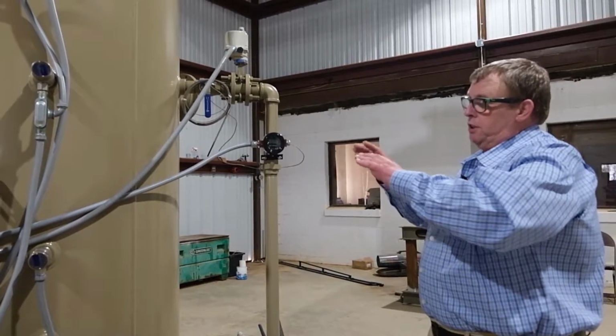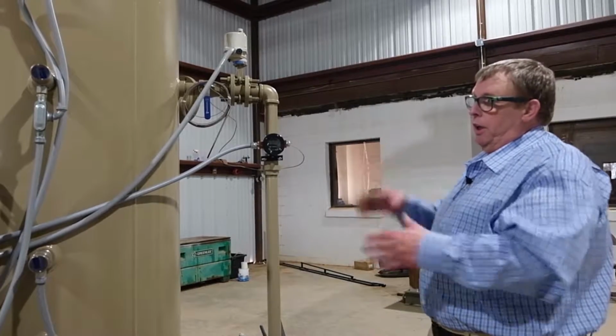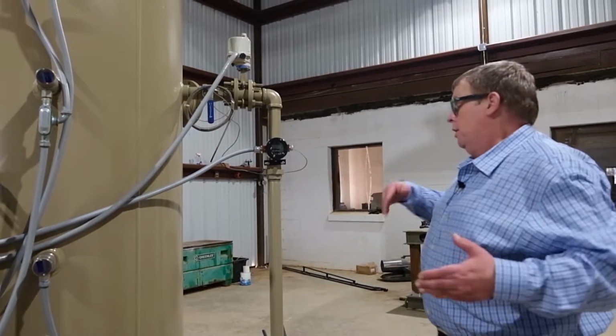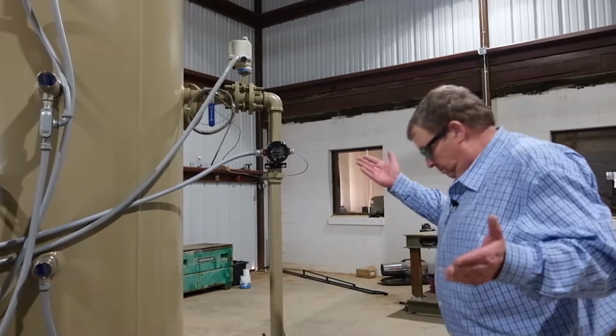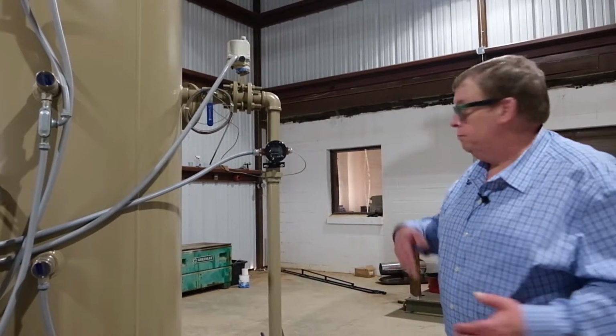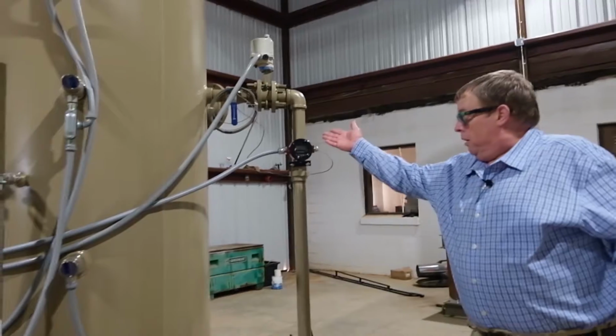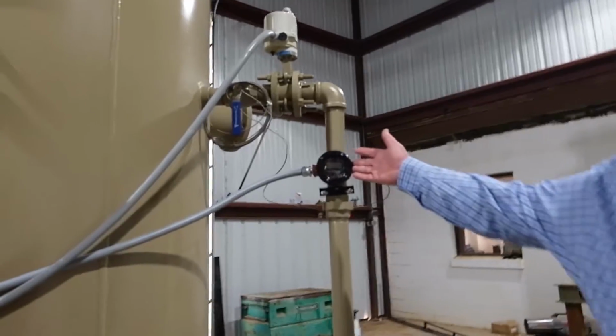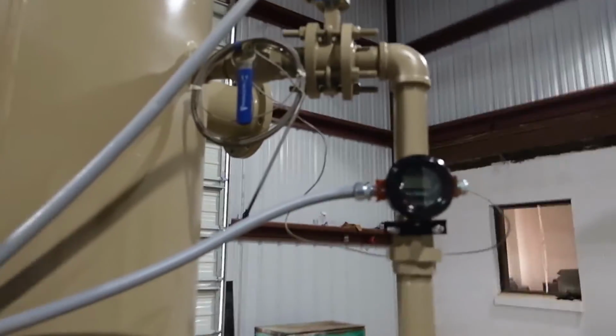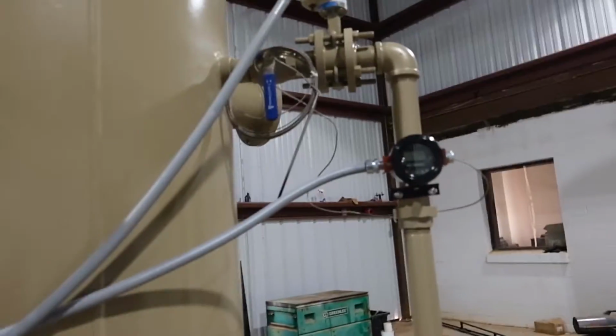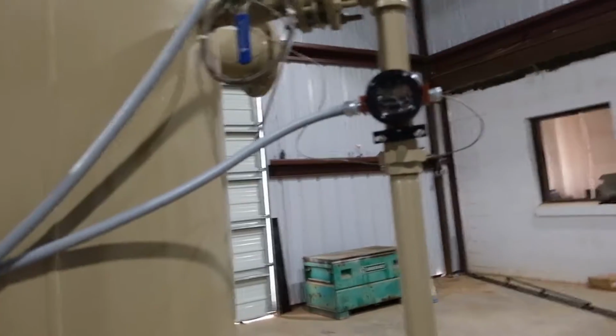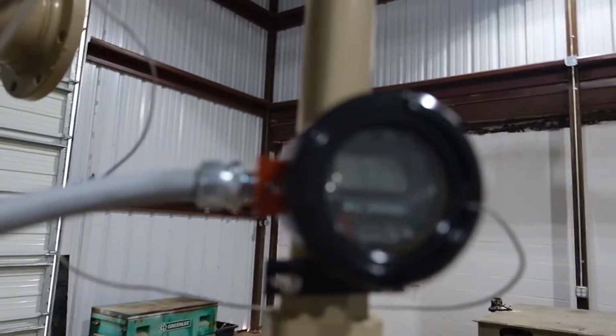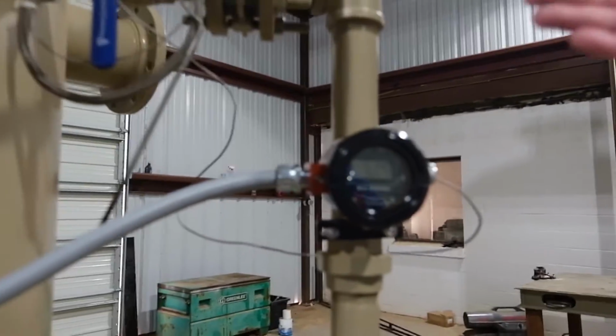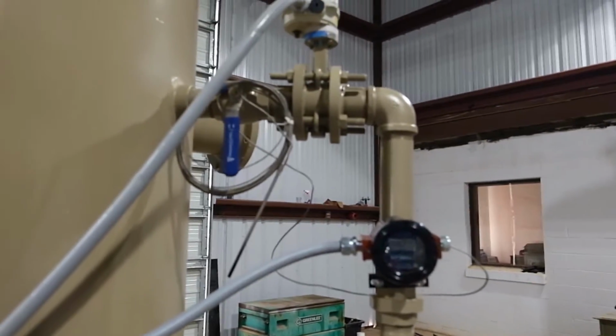We do have a system that could be completely enclosed inside your enclosure, but like we mentioned earlier, with Cimarex Energy, who we sell flares to, they like to have this display mounted outside of the control box, so that when their pumper pulls through the location, he can just see that he's got pilot burning. So that's going to give him a current temperature that the pilot is burning at this time. You also see that we've displayed a K-type thermocouple probe, which is what we use.